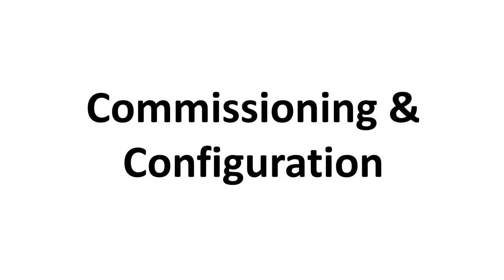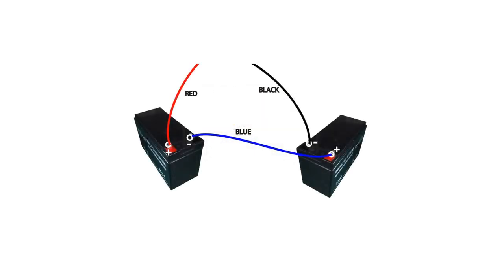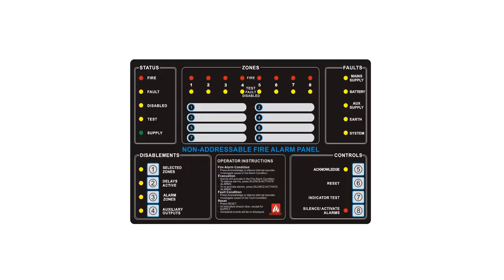With pre-commissioning checks completed, we're ready to complete the commissioning. This includes configuring the panel for optimal operation in the building and testing the devices and functions. First, turn on the main supply and fit the batteries, taking care to ensure the correct voltage polarity. The green supply LED should be the only indicator illuminated. If fault or other indications are active, resolve the causes.